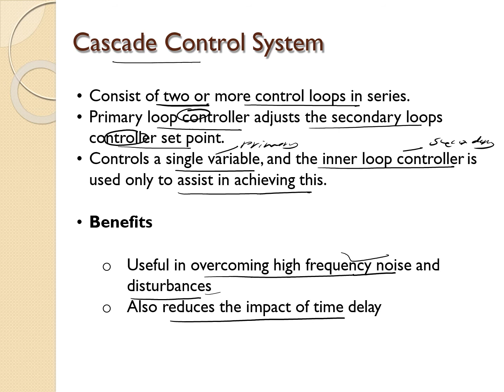So key features for a cascade control design to be successful. The secondary loop should reduce the effect of one or more disturbances. The secondary loop must be at least 3 times faster than the master loop. If we talk about faster, normally flow control or level control is one of the fastest control loop systems. So the secondary loop should be tuned tightly.